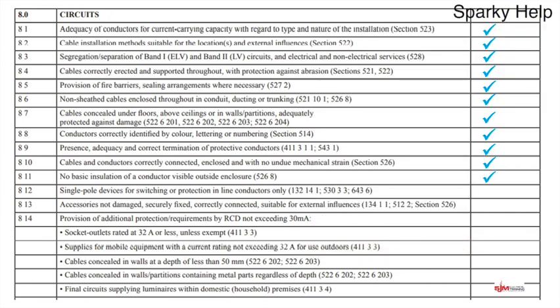Single pole devices for switching or protection in line conductors only. That's more of a visual check, though it can involve testing too. We're making sure that the switches have got the line conductor, and you can see that's the case. Obviously if you wired all this you know anyway, because hopefully you did it as you went along — but you're about checking it.